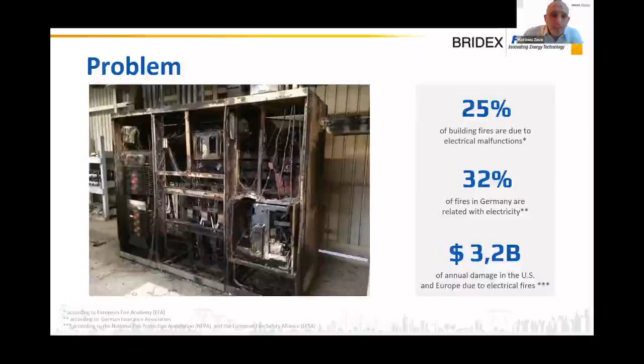The reasons for these fires and overheating in the first place can be multiple inside switchgears and switchboards. The most common one is loose connection, but also aging of the equipment. By aging, we mean that switchgear, after a certain number of operations, gets increasing contact resistance, so it overheats. Then you get arc faults, insulation failures, overloads, or improper selection of equipment — for example, when your switchgear doesn't have the proper rating for the current it's carrying.